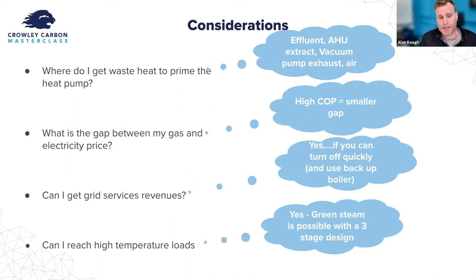The second consideration is the gap between the gas price and the electricity price. You've got to put electricity into the heat pump to run it - that costs money, and it's displacing gas or oil, preferably oil, because oil and LPG are more expensive than gas, although gas is very expensive at the moment. So what's the gap between those two things, and does it pay to put in a heat pump? Ideally, you want a COP or an efficiency to be as high as possible - they range from 2 to 6, depending on the configuration of the heat pump and the gap between the two temperature levels. That consideration is key to getting a payback, as well as getting the decarbonization by running the heat pump on green electricity.